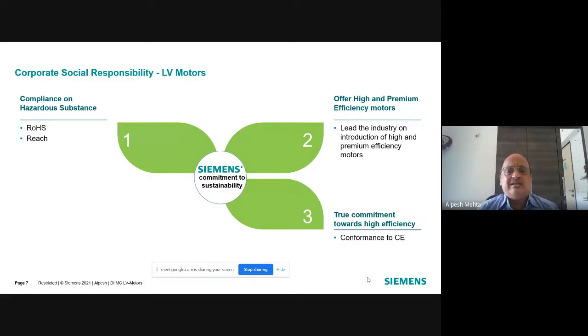Since it's driven by IEC, any product conforming to CE marking must comply with this guideline: when marking CE on a motor, the manufacturer must produce a type test report revealing that the tested efficiency is more than the nominal or declared efficiency.